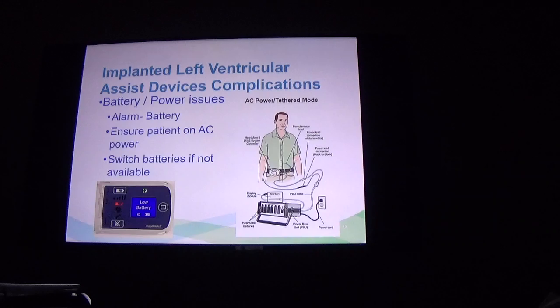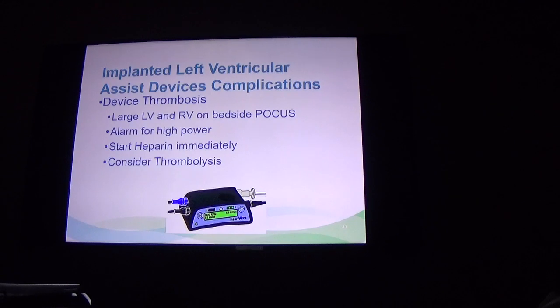So again, I keep saying the battery because this is probably one of the most common, most dangerous alarms, because if they're on battery mode and it runs out, the pump's just going to stop. So, bye-bye. Make sure they're plugged into AC at all times, and then switch batteries if that's not available. Again, hopefully they brought some spares.